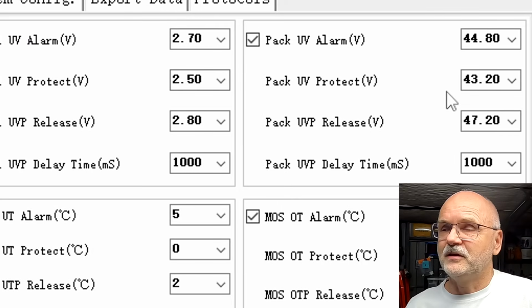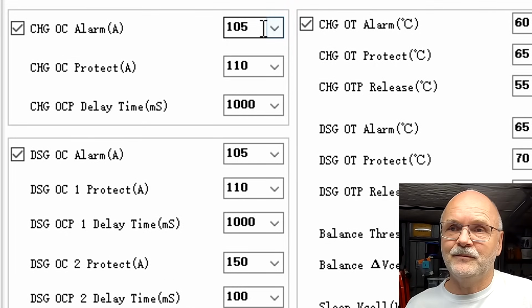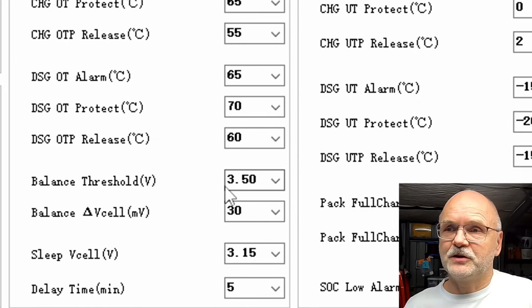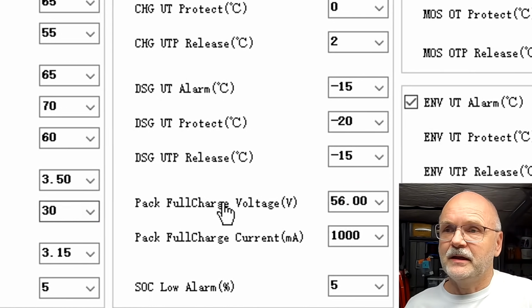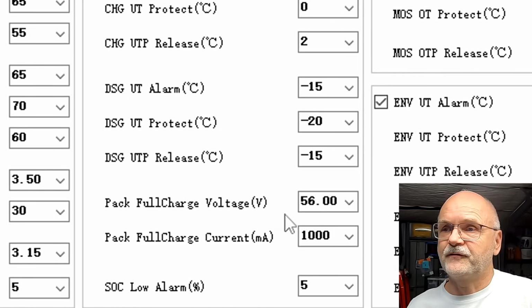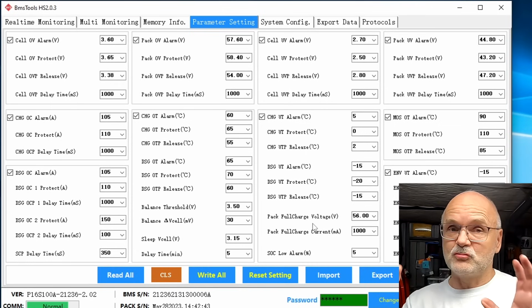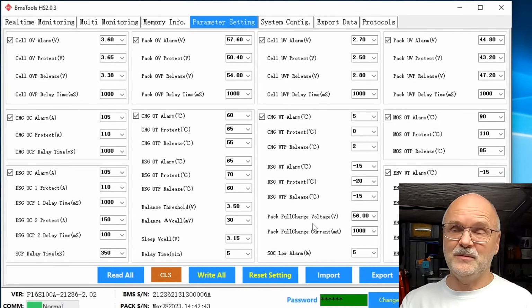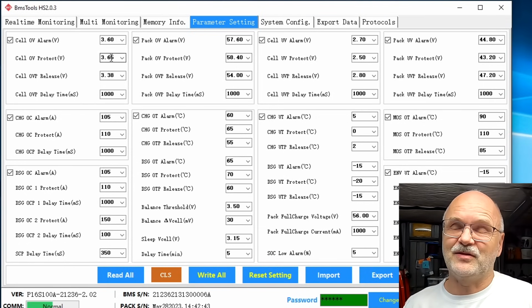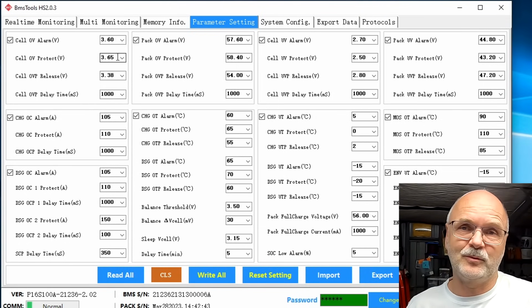58.4, 43.2 at the lower end. We've got 105 amps. Alarm, 110 is the protection, and the same for the discharge. Balanced start voltage, 3.5. And the pack full charge voltage is 56 volts. So you can actually run the whole battery with these default parameters, settings, and it will be fine, it will be working. I just would set this one here to 3.65 instead of 3.7.